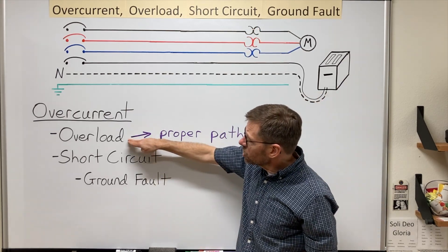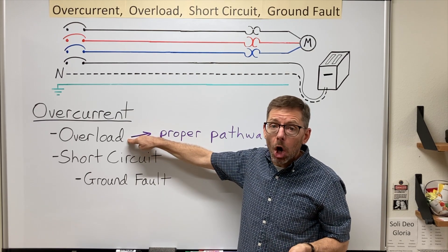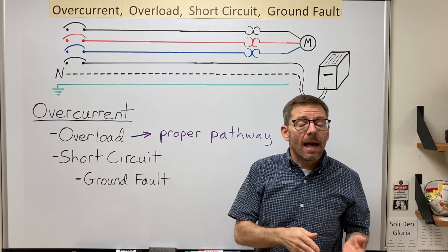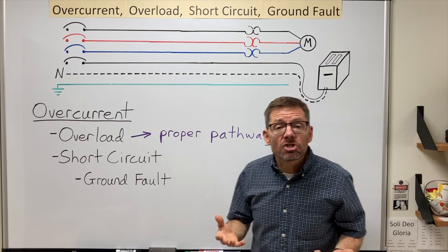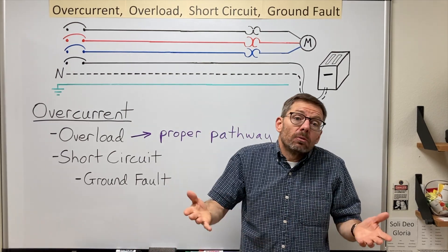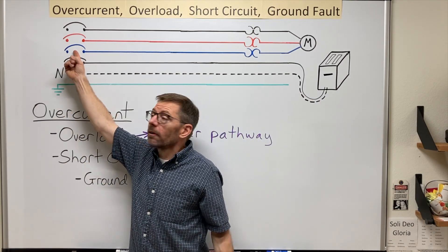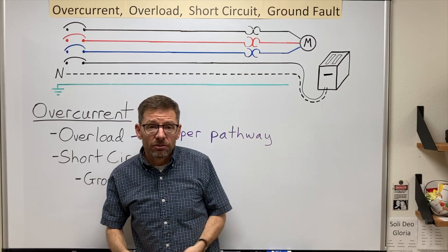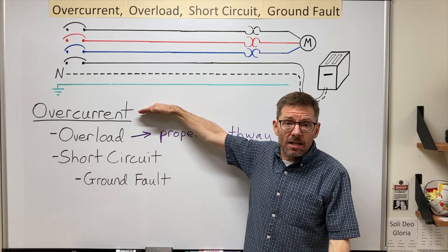Now this definition goes on to tell me that if the excess current continues for too long, it can cause damage or dangerous overheating. But there are safe overloads, ones that last just a few seconds, even a few minutes, or sometimes longer, depending on the intended characteristics of the devices involved. And there's an info note under this definition that addresses that issue.